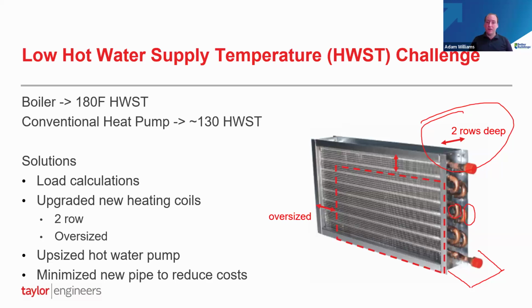The more rows deep, the more heating capacity you get, but there's also increased air side pressure drop. And we're trying to reuse the existing supply fans, so we didn't want to increase it to 3 rows. We did a 2 row deep coil as a good compromise. And then the other thing you can get is oversized coils. So let's say you need a 10-inch VAV box, you can ask the manufacturer to give you an oversized VAV box, and they'll give you a 12-inch VAV box with a 10-inch inlet. So you get a bigger coil, and that gives you more capacity and a lower air side pressure drop because the air is going slower through that coil.